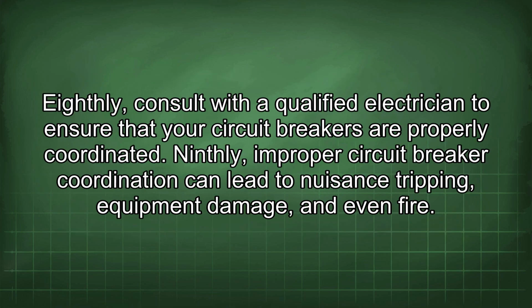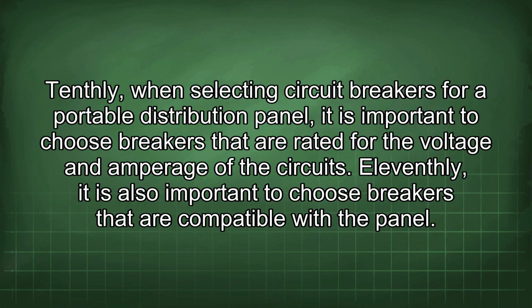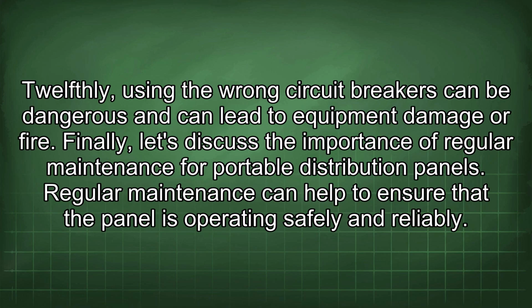Eighthly, consult with a qualified electrician to ensure that your circuit breakers are properly coordinated. Ninthly, improper circuit breaker coordination can lead to nuisance tripping, equipment damage, and even fire. Tenthly, when selecting circuit breakers for a portable distribution panel, it is important to choose breakers that are rated for the voltage and amperage of the circuits. 11thly, it is also important to choose breakers that are compatible with the panel. 12thly, using the wrong circuit breakers can be dangerous and can lead to equipment damage or fire.